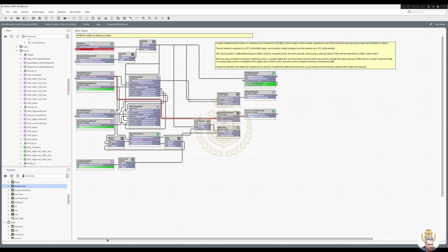Right, if none of them are on, these valves will remain closed until any relevant unit goes into operation. Okay, so I need the enables, and it requires a cold water feed to be open. This will be determined from a BACnet point transferred from the CRAC, so I'll put the enables in an AND. The BACnet point, so BACnet, open valve, CRAC number 1. Pin slots. That's going to be an open or a closed. That's going to be my command from there.